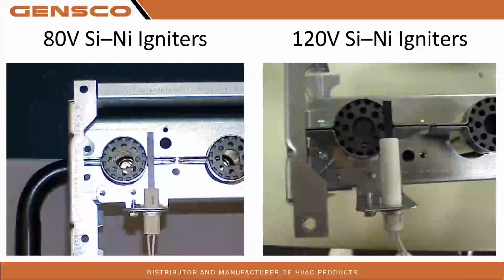Like I said, if you go with an aftermarket for convenience, or it's a Saturday call and you don't have that exact igniter, make sure it's lighting like it should. Actually get in there with a mirror and make sure that hot spot is where it needs to be to light properly.